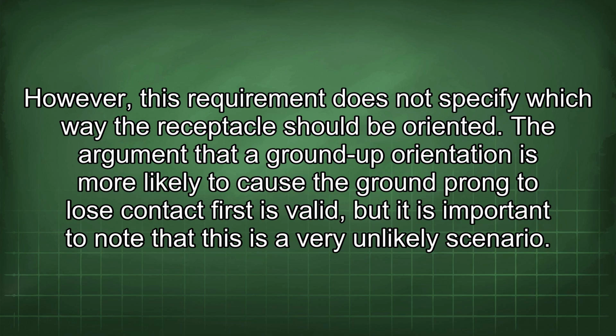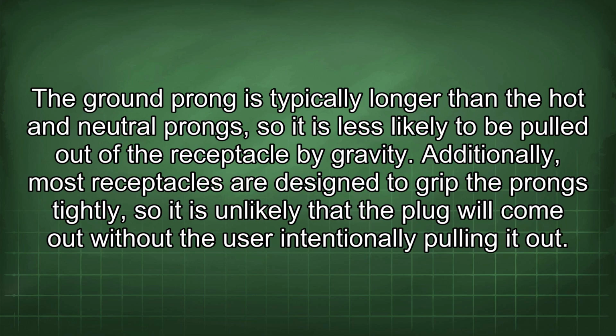The argument that a ground-up orientation is more likely to cause the ground prong to lose contact first is valid, but it is important to note that this is a very unlikely scenario. The ground prong is typically longer than the hot and neutral prongs, so it is less likely to be pulled out of the receptacle by gravity. Additionally, most receptacles are designed to grip the prongs tightly, so it is unlikely that the plug will come out without the user intentionally pulling it out.